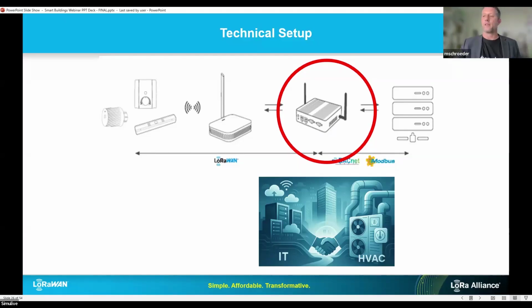The gateway converts all LoRaWAN data points 100% automated into Modbus and BACnet data points. That means no IT knowledge is needed, no programming skills needed. The only thing you have to do is set up your gateway and connect it with the converter. In the building management system, you will see all the new data points in the same quality and structure as hardwired sensors.